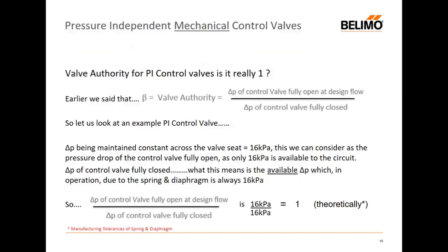Just moving now to the calculation on valve authority, but with pressure independent control valves in mind, let's redo the calculation. We said earlier that valve authority is the pressure drop fully open at design divided by the available pressure, or the pressure when the valve closes. So let's look at a PI example. The pressure drop we saw earlier was being maintained constant across the valve seat at 16 kPa. So we can consider that as the pressure drop of the control valve fully open. And then because it's maintaining only 16 kPa to the circuit and the KV changes, then we can say that the available pressure is 16 kPa. So 16 through our control valve divided by 16 kPa available gives us our theoretic value of 1.